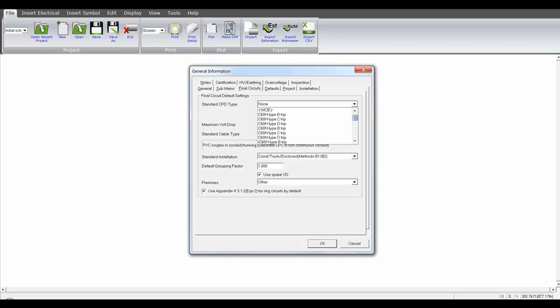We can select our preferred protection on our final distribution boards. We do have the ability to change that on a board by board basis completely or individual ways. Again, there's the allocated volt drop, the cable type, the installation methods, and the premises type, which will determine the diversity at board level, which will be explained in a future video.